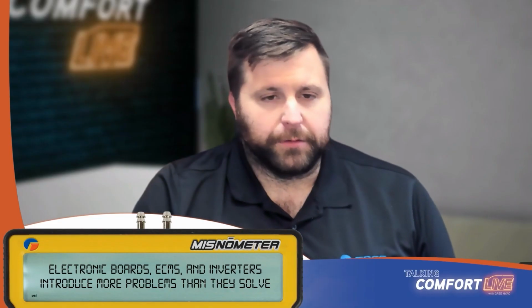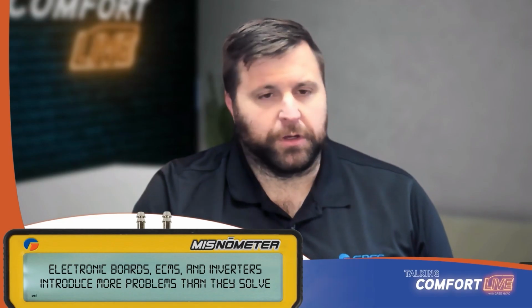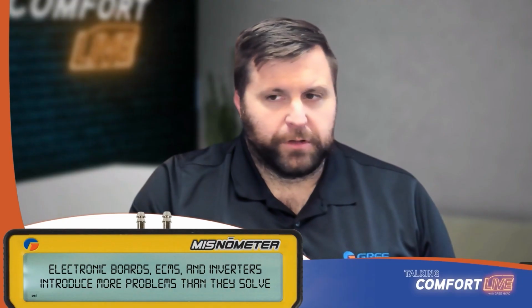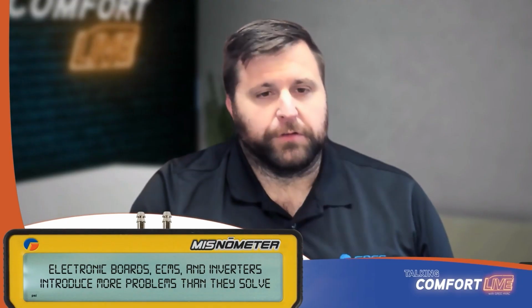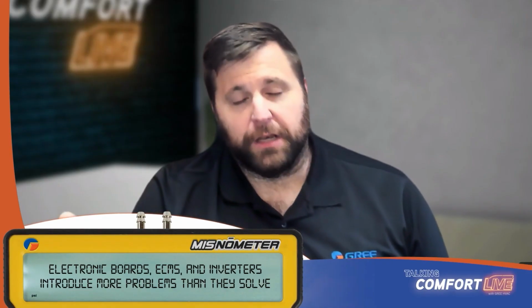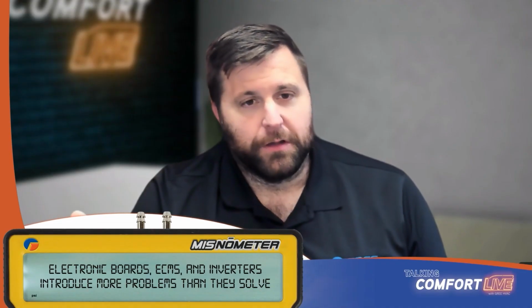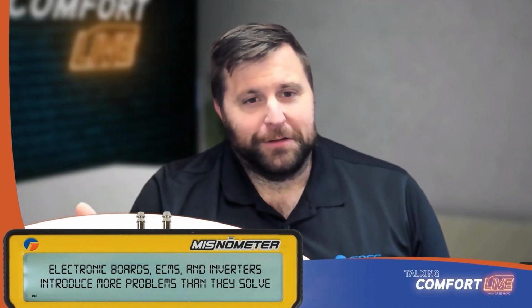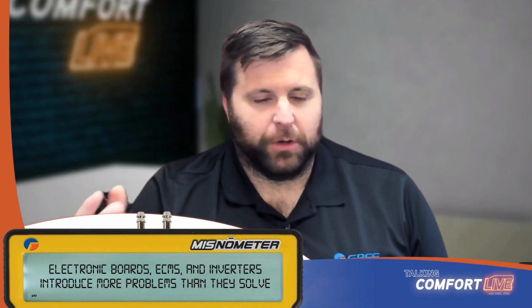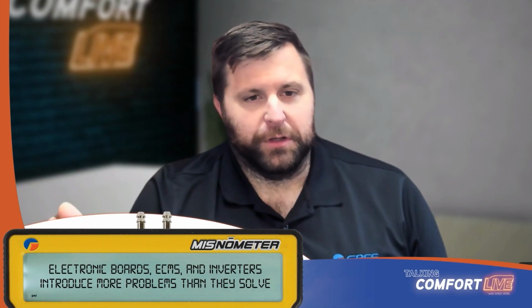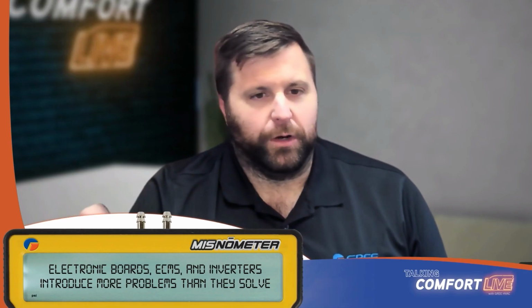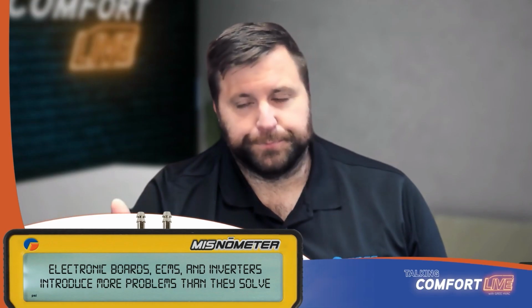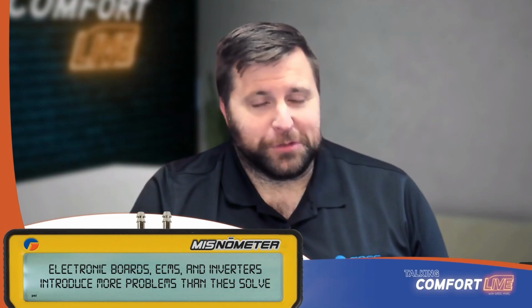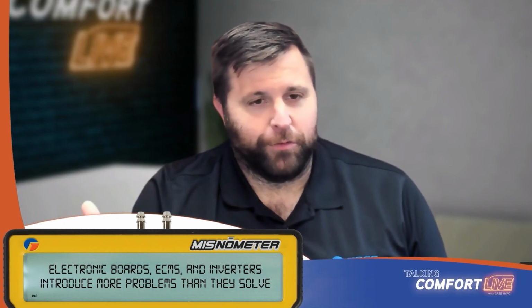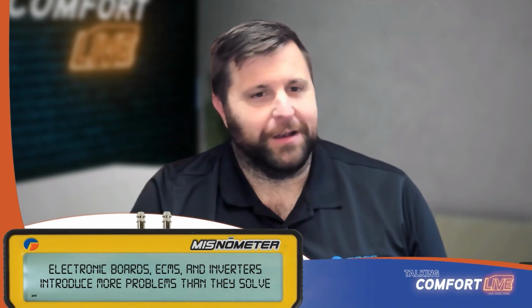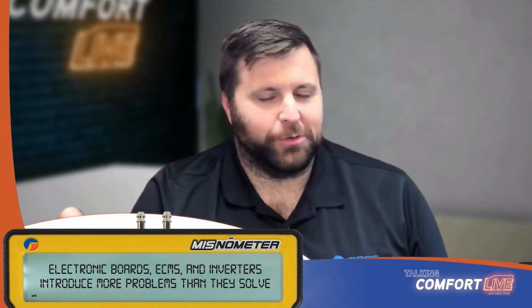There's also the reason why this stuff gets added, and that's efficiency. We add inverter boards, ECMs, and all the rest of that stuff for efficiency. You can look at it this way if you'd like. If you're familiar with the M1 blower test for SEER ratings, all they did was choose a higher static pressure, which is more common in the field. Previously they had tested at 0.1 inches water column. Years ago, that was realistic. You could possibly have a duct system like that. But if you've got a 4-foot plenum or a spider box or something like that, you're not running on 0.1. You're going to be closer to 0.5.